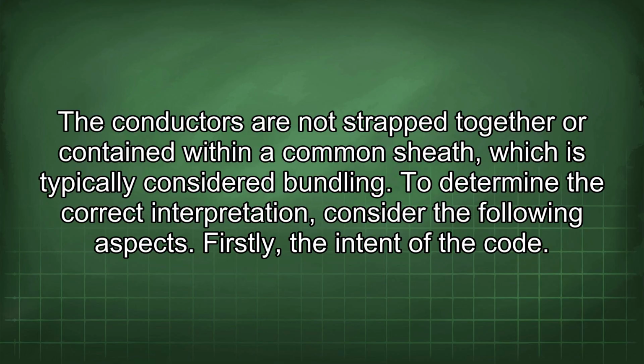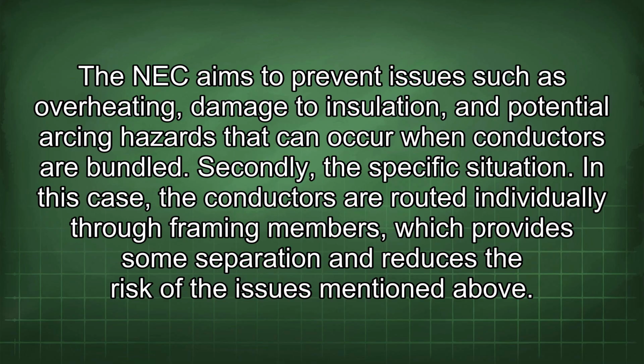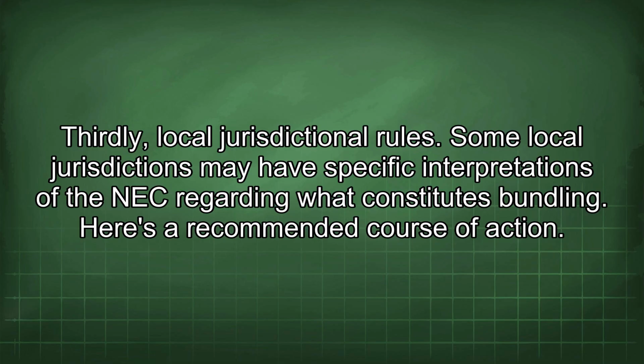Firstly, the intent of the code. The NEC aims to prevent issues such as overheating, damage to insulation, and potential arcing hazards that can occur when conductors are bundled. Secondly, the specific situation. In this case, the conductors are routed individually through framing members, which provides some separation and reduces the risk of the issues mentioned above. Thirdly, local jurisdictional rules. Some local jurisdictions may have specific interpretations of the NEC regarding what constitutes bundling.